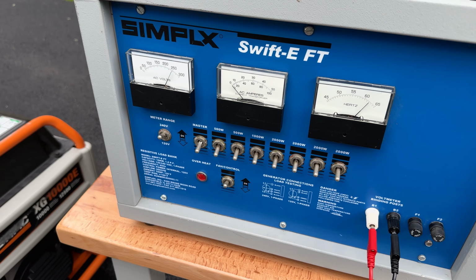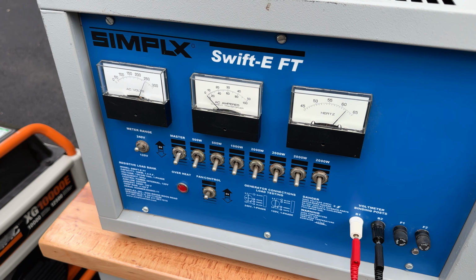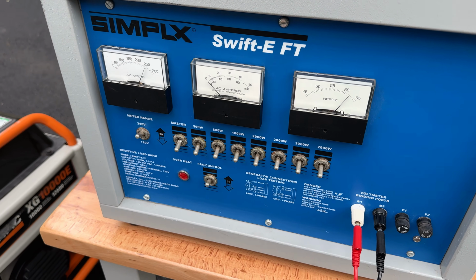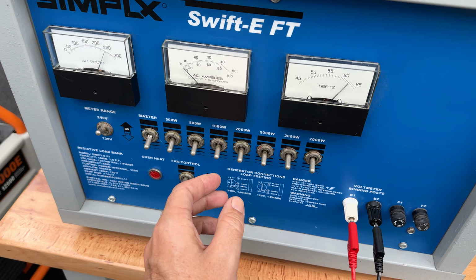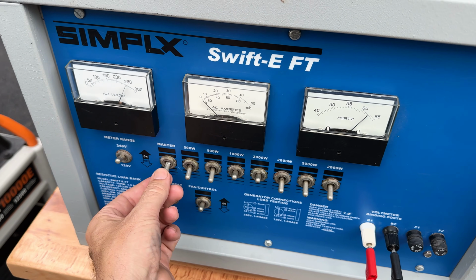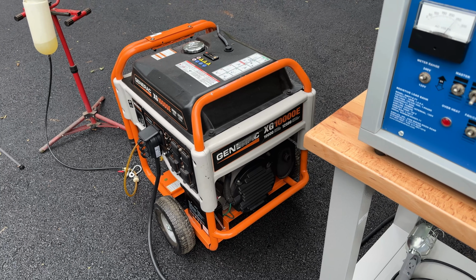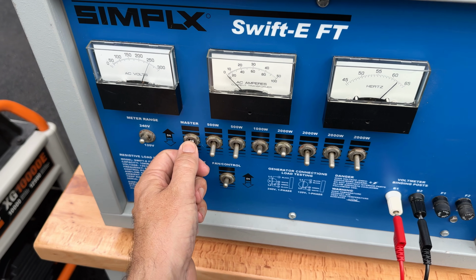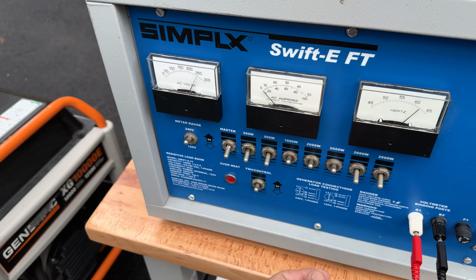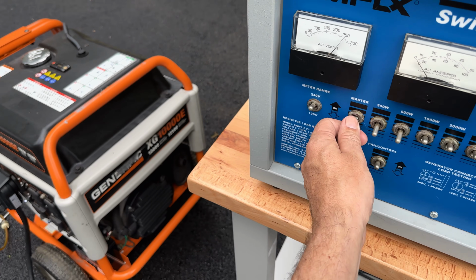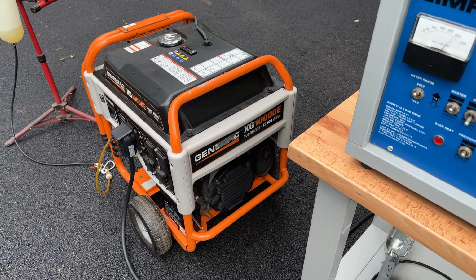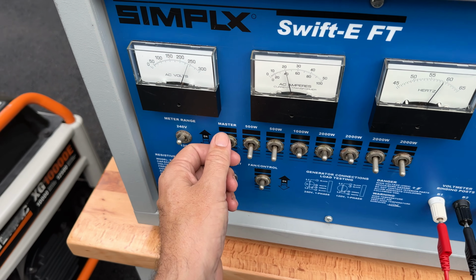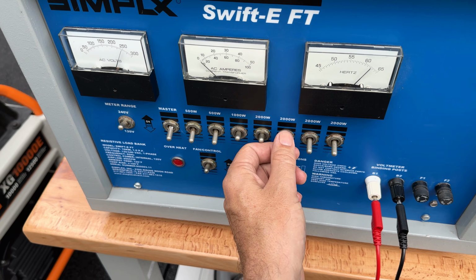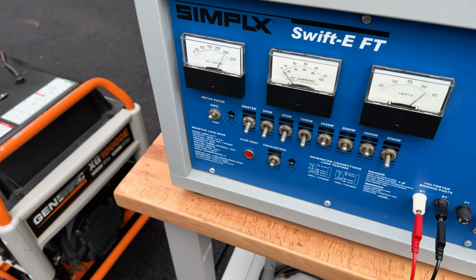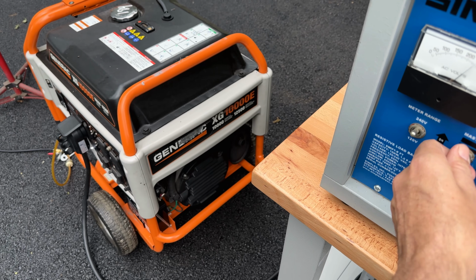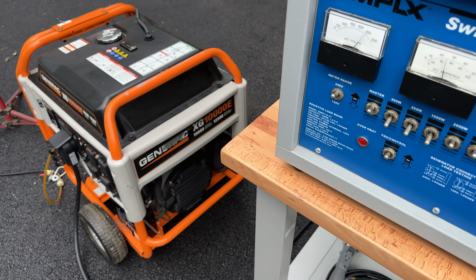Now I'm going to try putting a load on suddenly. With the space heaters, 1,500 watts is the max I'd put on at any one time. Right now we're at 0 watts — let's put on 3,000. No issues handling that, we'll turn the master off. Let's try 5,000, starting from 0 watts again — handled that all right. Let's try just a bit more, going from 0 to 6,000 watts. Not too bad, it handles it pretty well.